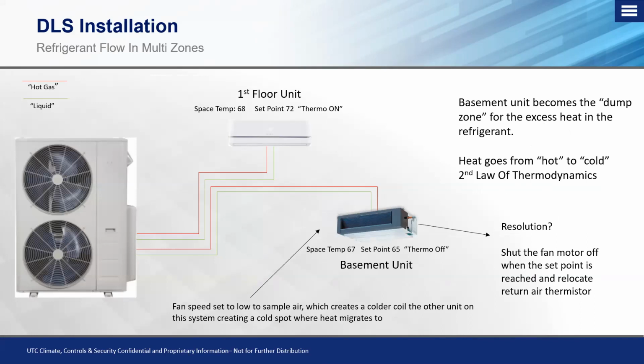So some things that we can do to try to deal with the overheating is first going to be, if we have an application, let's just say we have a unit in the basement, and we're not really too much concerned with what that basement temperature is. It's kind of just tempering that air. If it's a little bit too warm or a little bit too cool, it's not a big deal. Well, we can configure that basement unit essentially to be our dump zone.